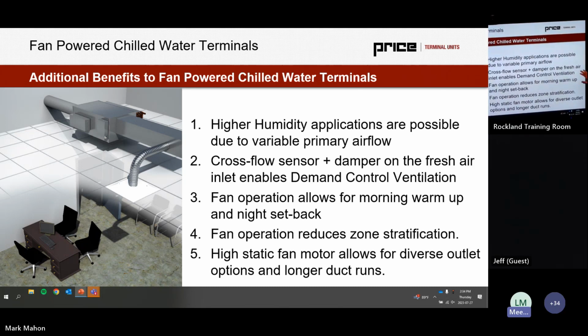So we can get demand-controlled ventilation, which I'll talk about more in a few slides. The fan operation allows for morning warm-up and night setback, so we can turn off that localized air handler. We can still recirculate locally, which means we can warm up the building in the winter months. And if we're looking in summer months and we needed to cool it down, that's not really common, but I guess you could do that. Usually the chiller is going to be off at night in most cases.